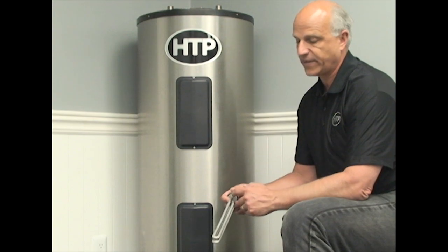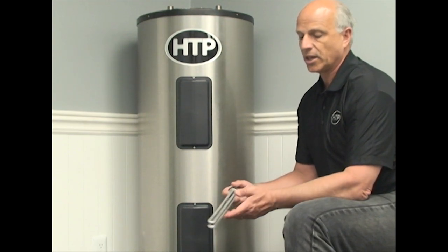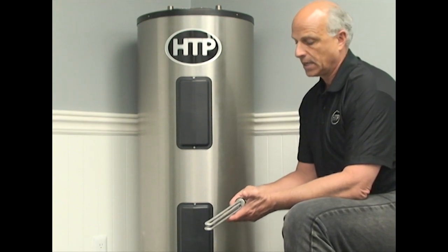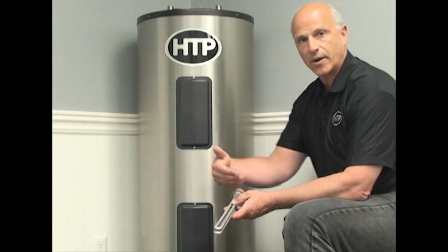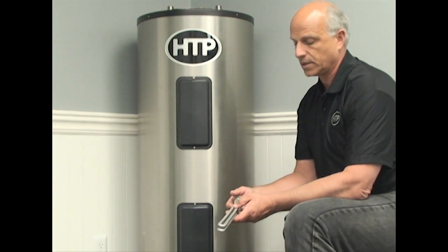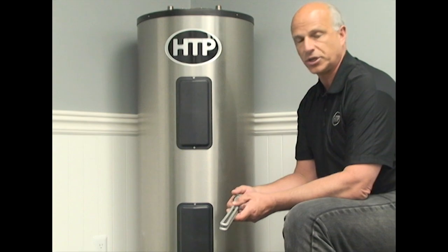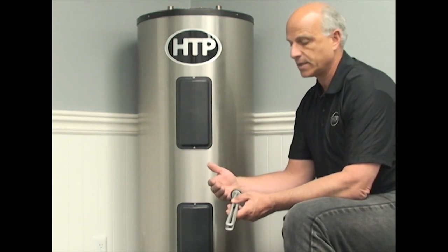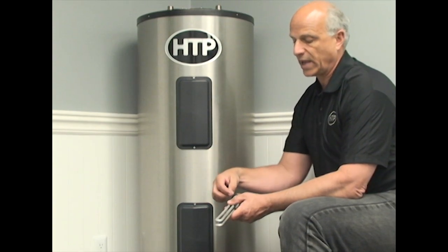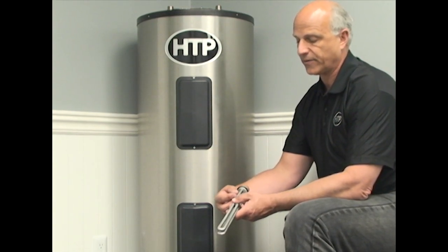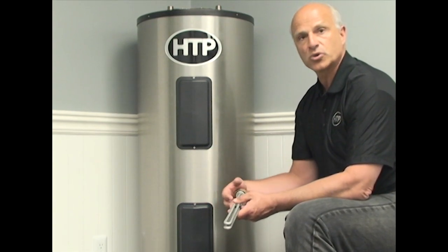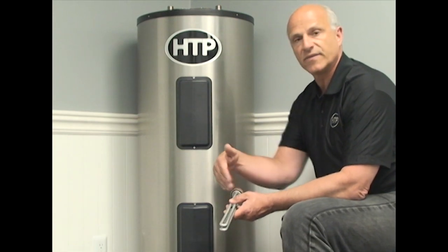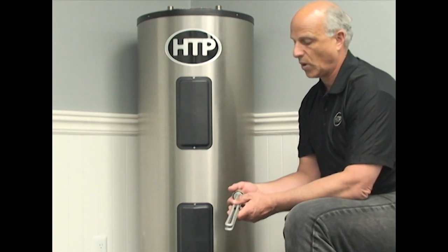One of the things on the design of the element is we made the element so it's very low watt density. It still gives you the amount of power you need to get into the tank and the amount of energy you need to transfer from the element, but the beautiful part about it is that we made it long so we have very small amount of energy we're putting in per square inch of the surface of the element which makes it a very low watt density element.